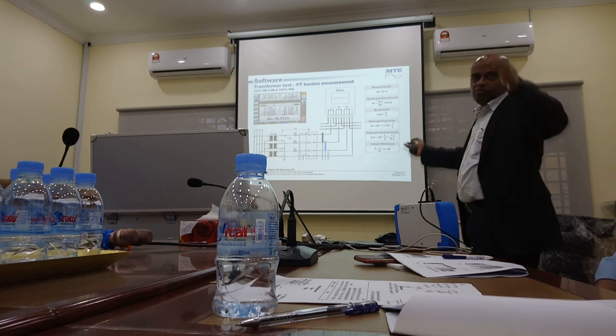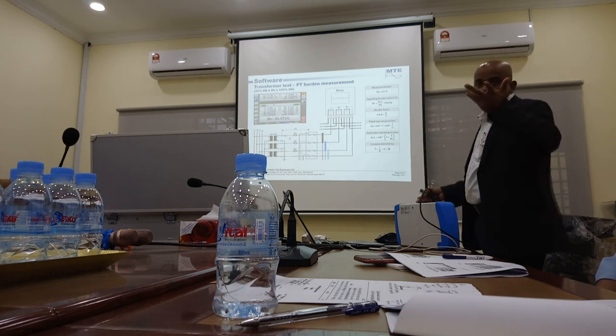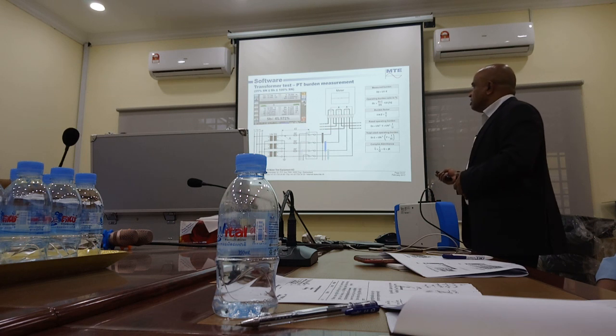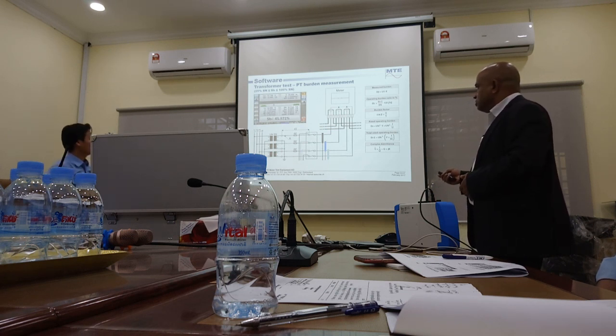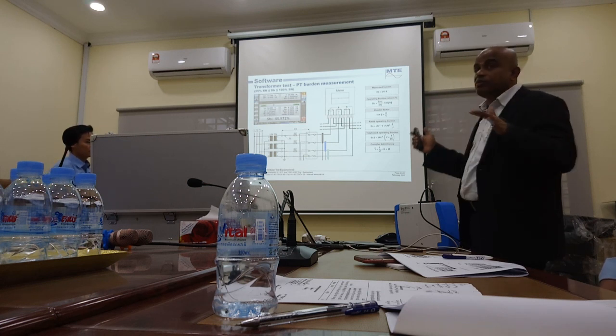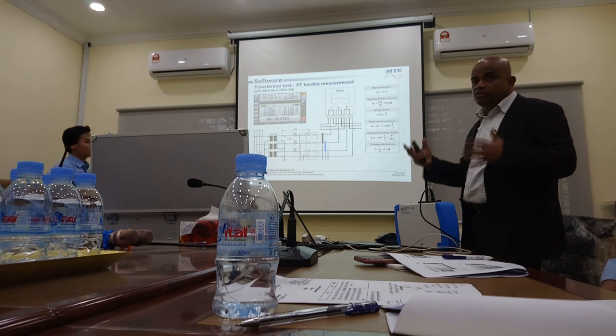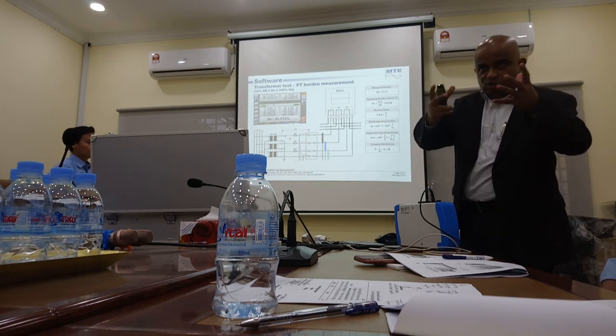Okay, because your plan and drawing will know how much length of cable, what is the diameter of the cable used, etc. If you don't key in the value, this value is useless. But this value is still valid. So this is all about measuring the power consumption of the meter. Why is the power consumption of the meter important, and the length of the cable, everything? Because that is the load to the PT.